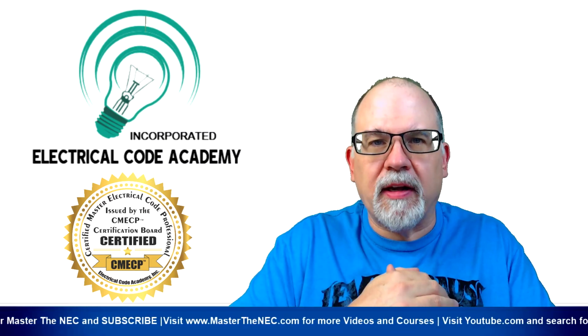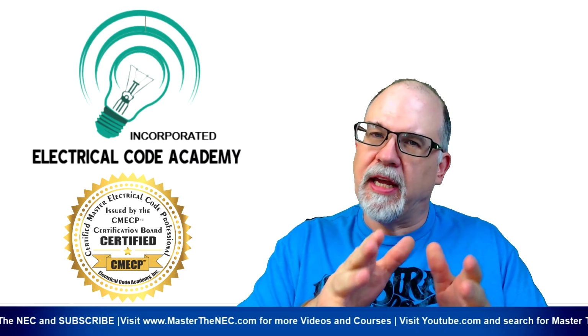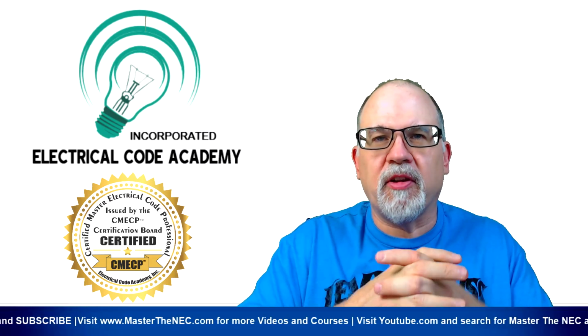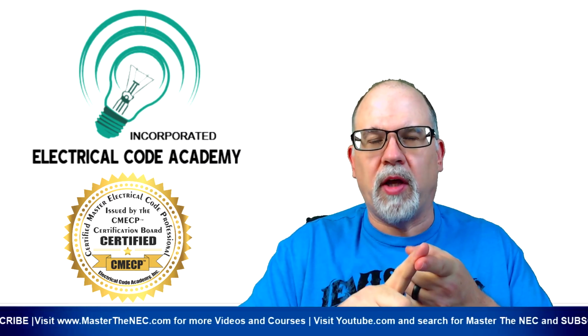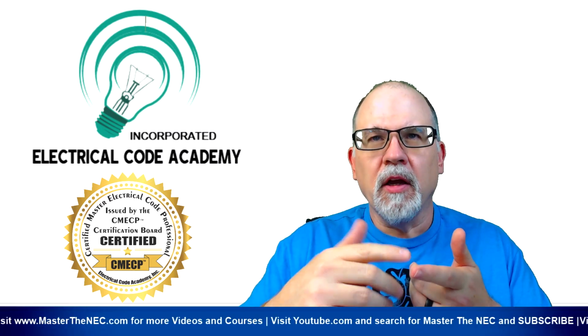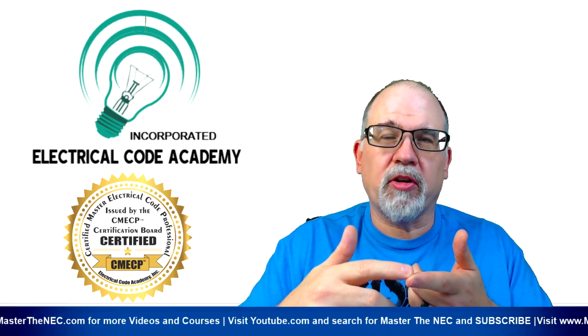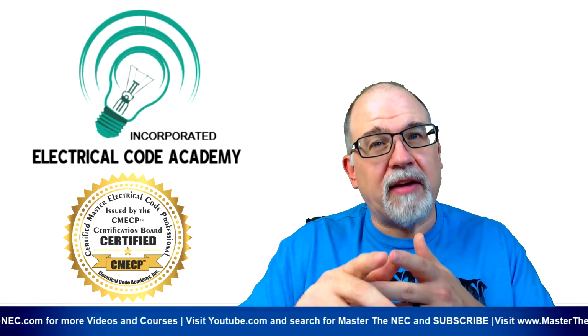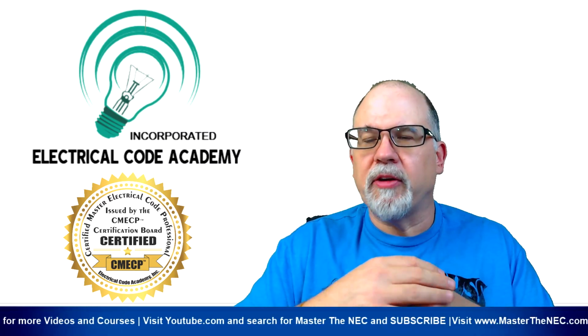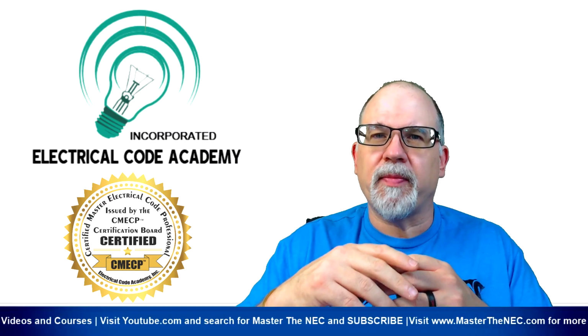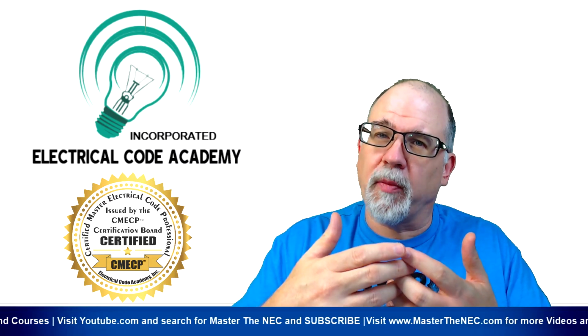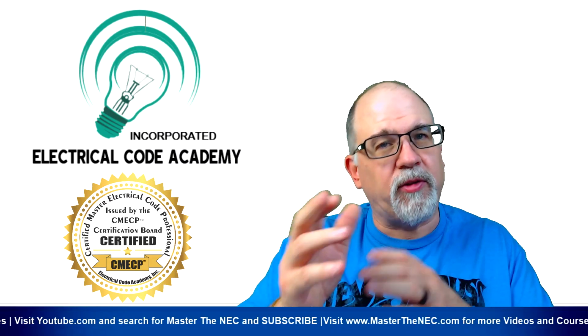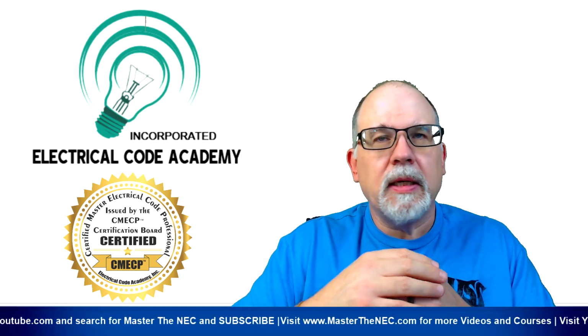Now, before I get started into that, I had a question that came in, and again, we've done other series up to this point. So you should have watched Series 1, where we talk about how to size the primary current on a transformer and the maximum secondary current on a transformer using the formula. In part 2, you learned how to size the overcurrent protective device for the transformer's primary and for the secondary, where applicable.